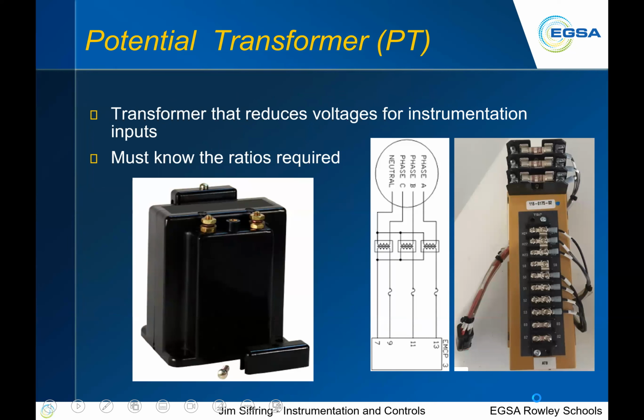Okay, PT, potential transformer. What is potential? Potential is voltage. Voltage and potential are pretty much used interchangeably here. So it's a voltage transformer, potential transformer, same thing. A transformer that reduces the voltage for instrumentation. So say your control panel can only take up to say 150 volt input or something like that. Yet you've got a 480 volt genset, or maybe you got a 4160 volt genset. You need some type of a device to lower that voltage down to where your control panel can actually see it. So there are different ratios.